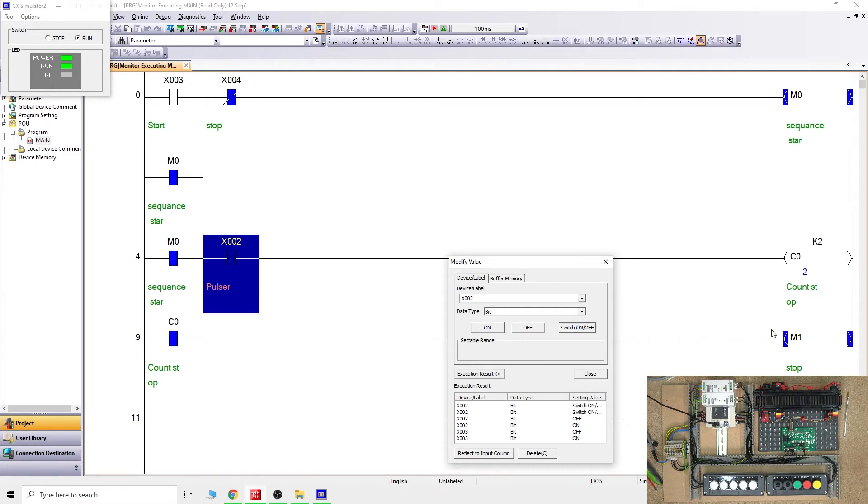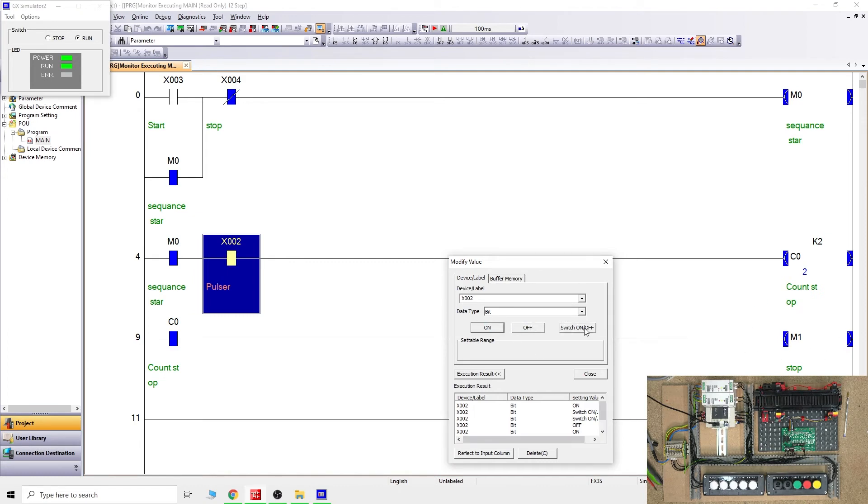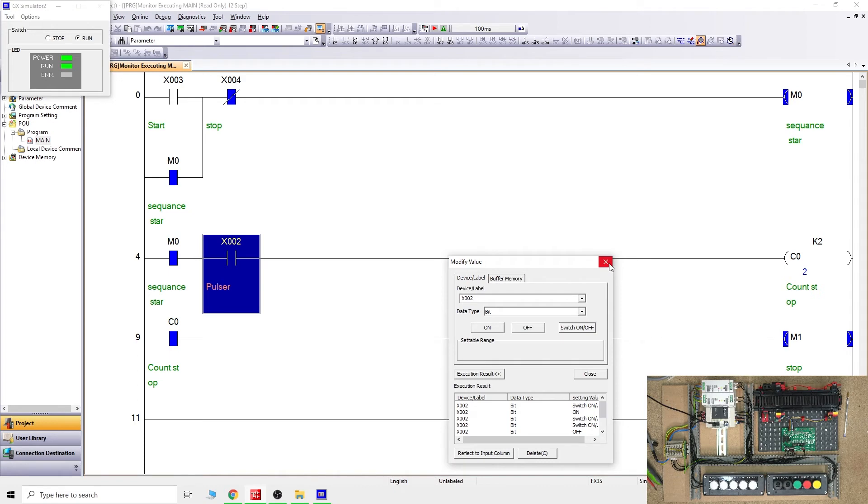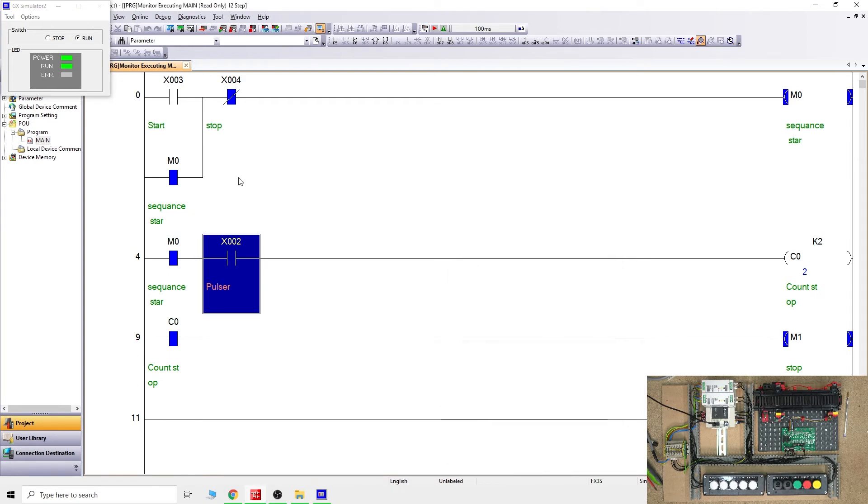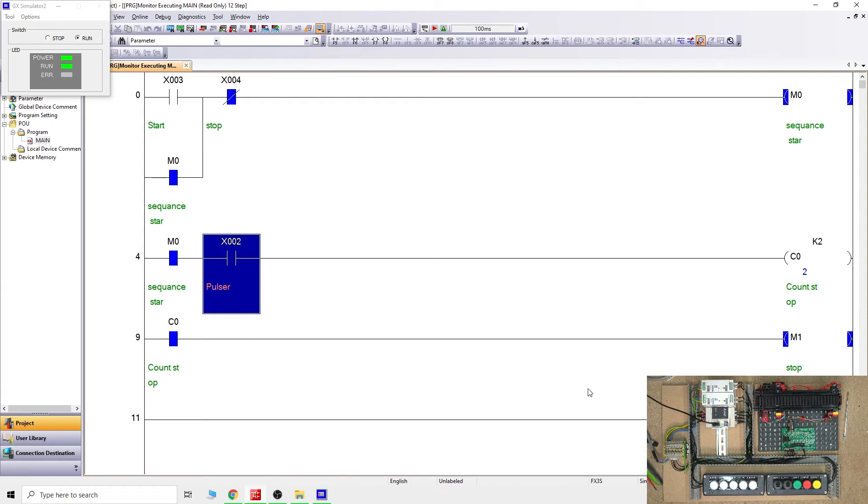As you can see, the counter is doing nothing because it's looking for pulses. We'll give it one pulse, then another one. As you can see, C0 has come on and M1 is on. If you do it one more time, nothing happens because it's set to go to two and that's all it's going to do. Because there is no reset, it will not reset itself. That's why it's very important for us to create some form of reset.